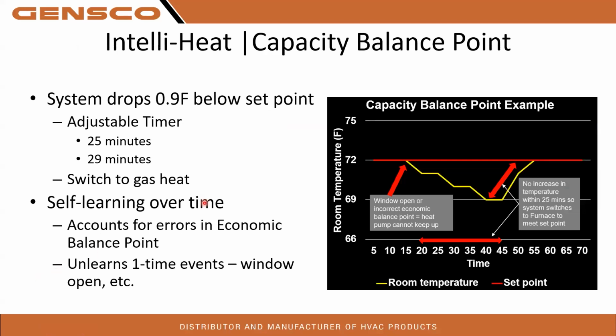Capacity balance points. So this is the fun part. These things are learning units. So what will happen is, even though you may have your capacity or economic balance point set to, say, 5 degrees, for example, if your system has been running for longer than 25 minutes and it sees that it's not dropping the temperature by more than 0.9 degrees below the set point or gaining any kind of temperature, it's going to automatically switch over to the gas furnace. Just saying, hey, I'm seeing my balance point is set to 5 degrees, but I'm at 18 degrees and I can't keep up. I'm going to switch over to the gas.